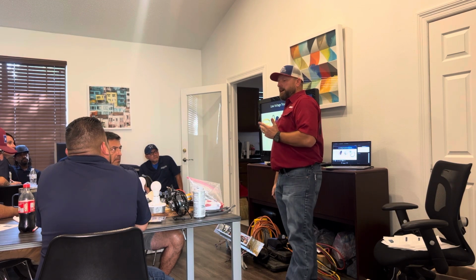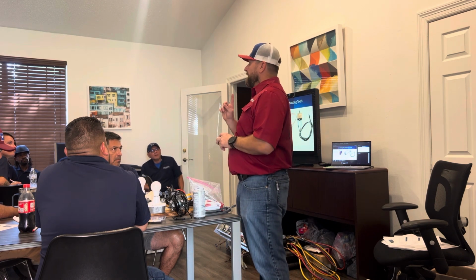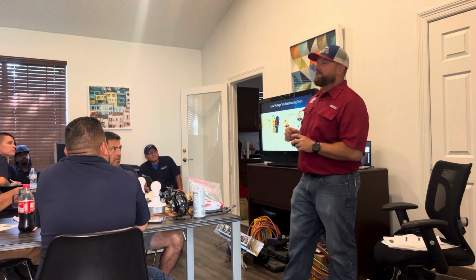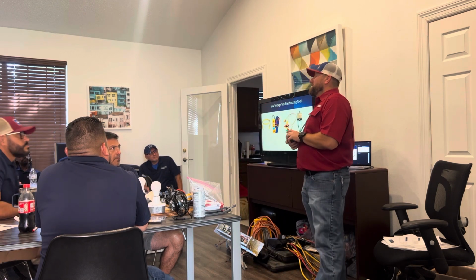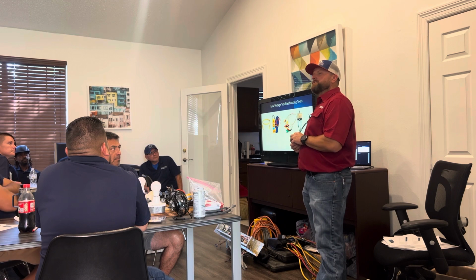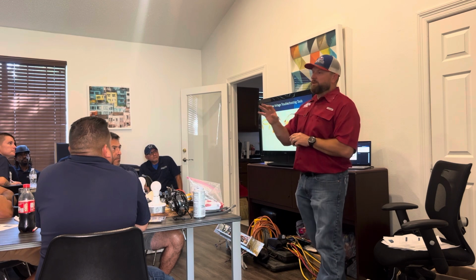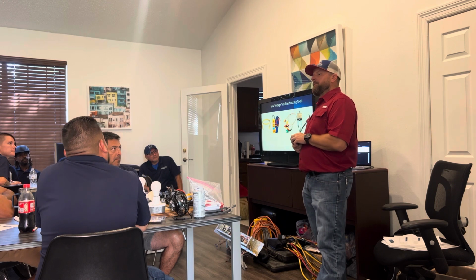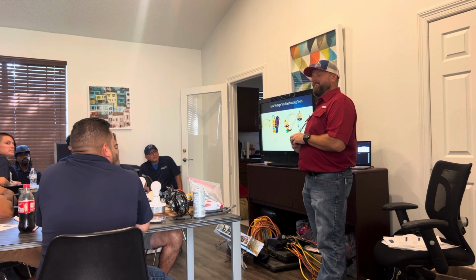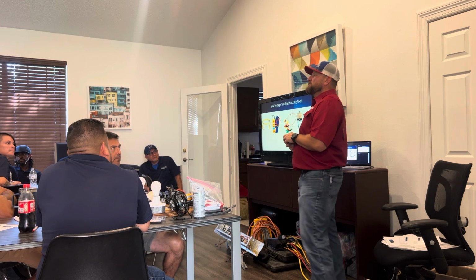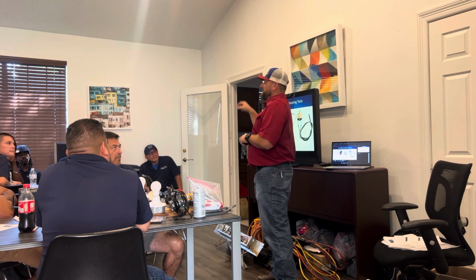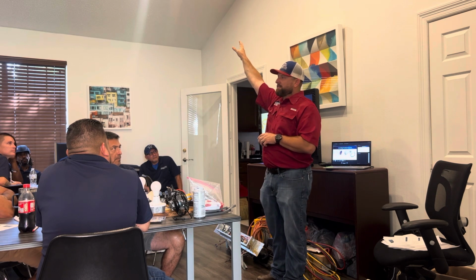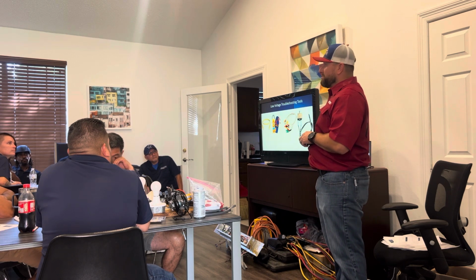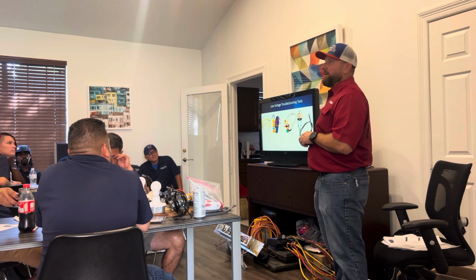I know I need to get to my next refrigeration part, but here's a way, a little more advanced, to know the transformer's working when you're at the thermostat with it still on the wall and no meter: your fan's running, and the outdoor fan running. That's right, fan running. So if you go to fan on, and that fan comes on, the indoor blower fan, that means the low voltage transformer's working, right? You can rule out a bunch of stuff right there just by turning that fan on.